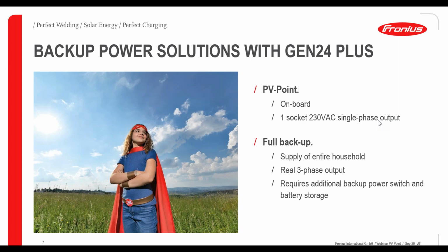And then on the other hand, we have the full backup solution. Here we supply the entire household, so we can have a real 3-phase output, but this requires an additional backup power switch. You need different contactors and relays in the switchboard to switch over from grid-connected mode to off-grid mode. Therefore you need separation, and therefore you need these components. But as I said, this is not necessary when you have a PV Point. Also, the full backup solution needs the battery storage, and without that it would not work.